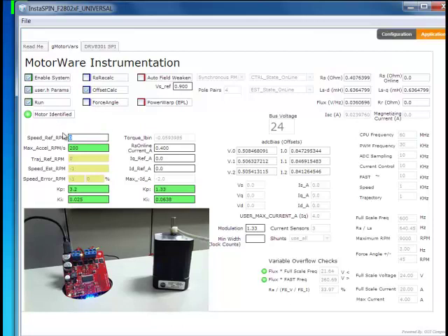So let's try a couple low speed options. This is 15 RPM per 1 hertz for this 8 pole motor. So we could try 5 hertz and check our speed controller here, and it's doing okay. You can see it's stable, but with the oscillation, it's moving around our set point pretty decently. So we can tune this a little better if we like. Probably needs to be slightly stiffer.